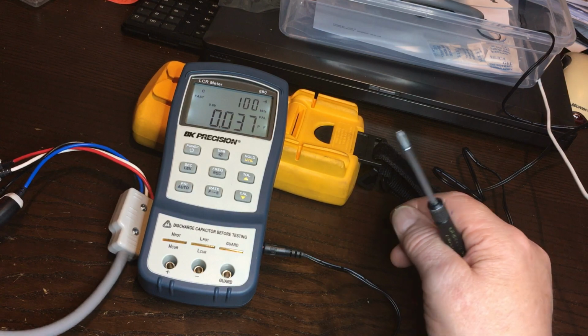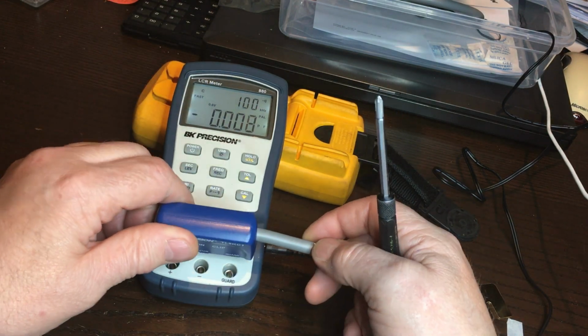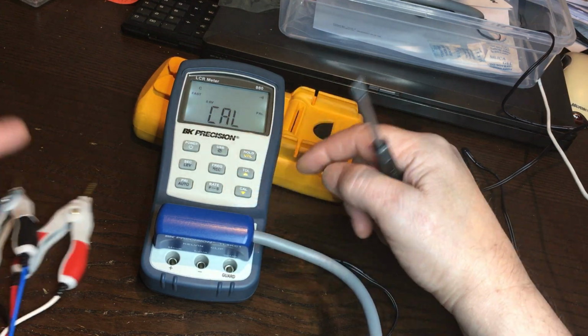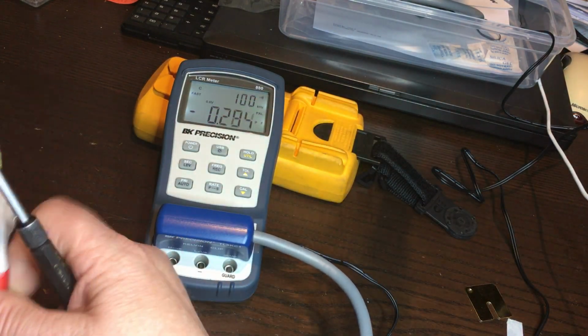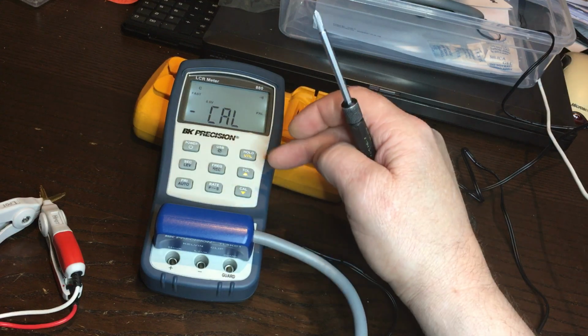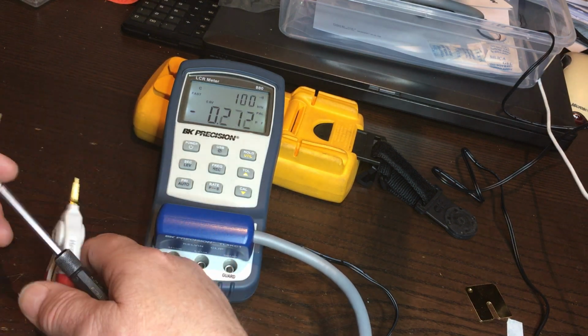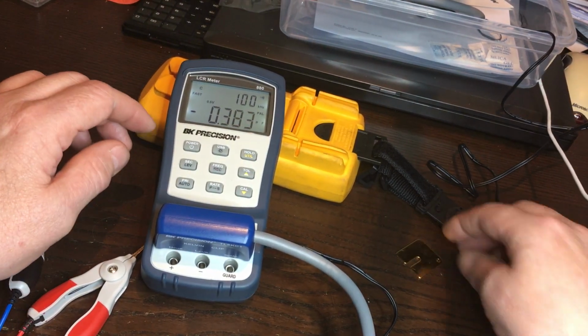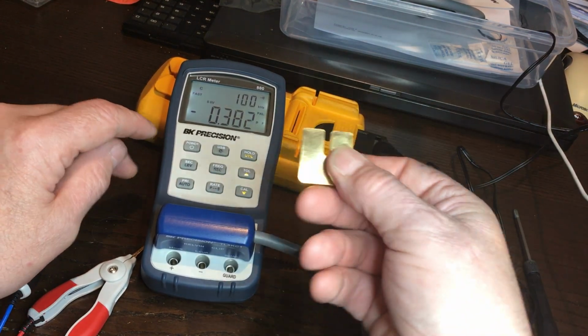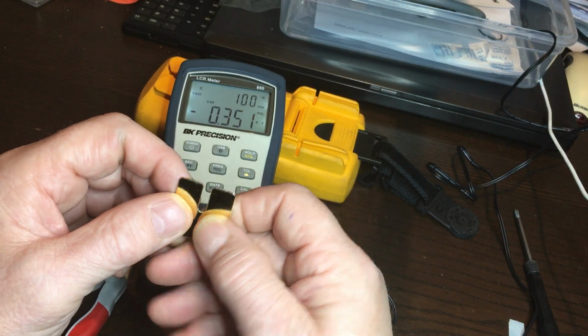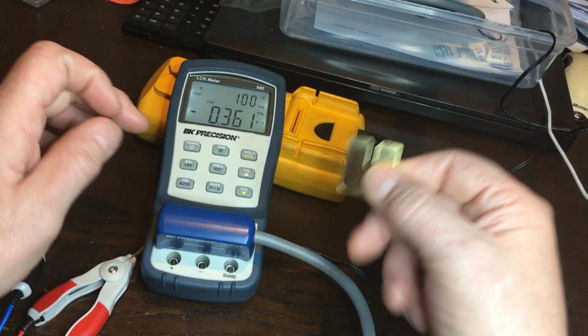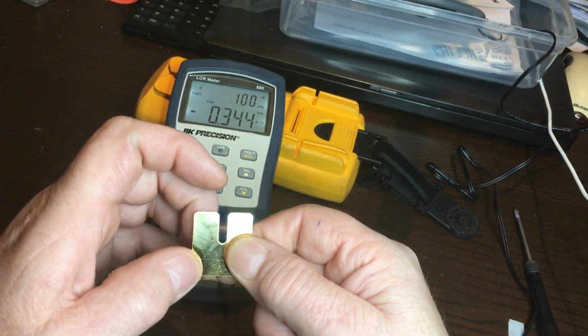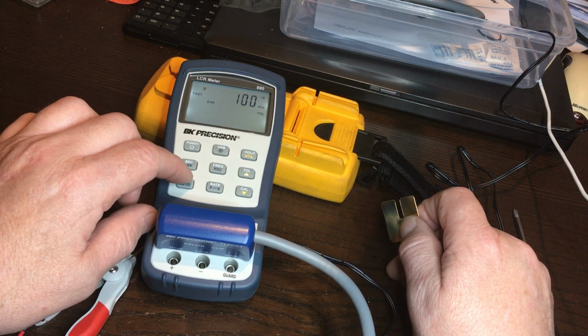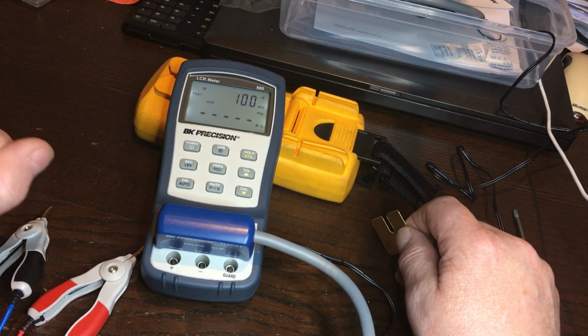The same goes for using the Kelvin clips. You stick in the Kelvin clips, you put it on calibrate, it says calibrate open. Well, it's open at this point, so that's confirmed. You connect them together, you put it in short, calibration short, and now it's calibrated for the Kelvin clips, and it can do crazy accurate measurements. So let's do that with a resistance measurement. This is a gold-plated piece of bronze, I think. Not sure what it is. I think this is a piece of bronze which has a little gold plating on it. So we put it to resistance. It's in megohm.